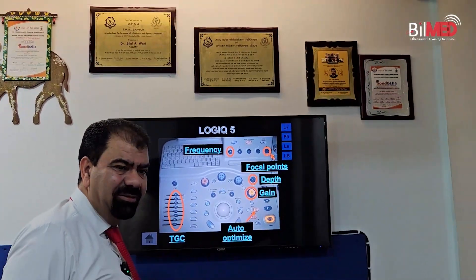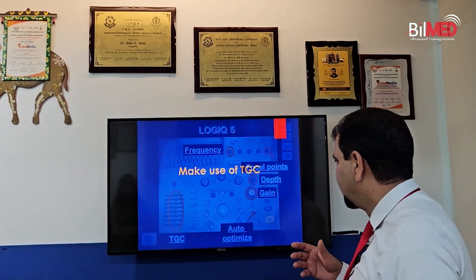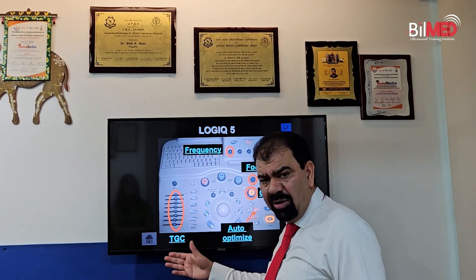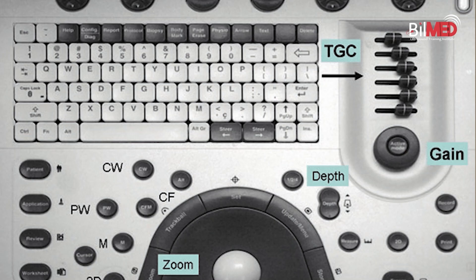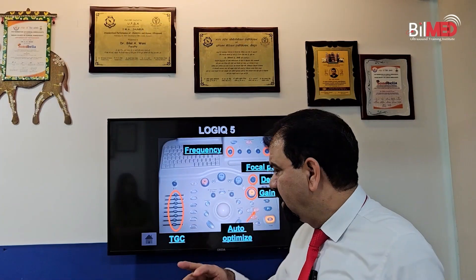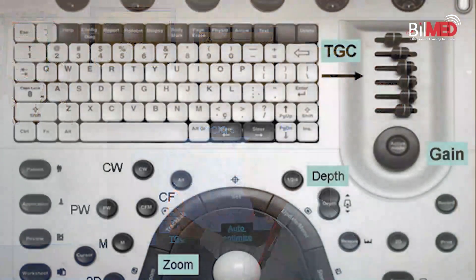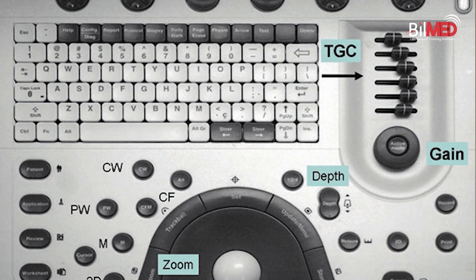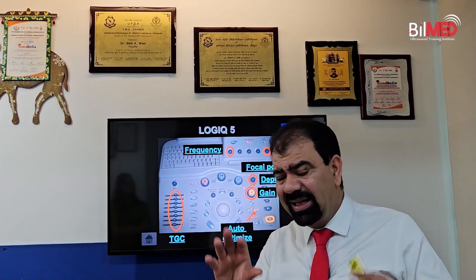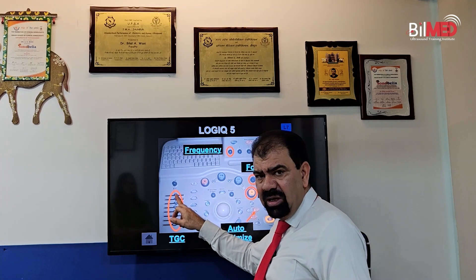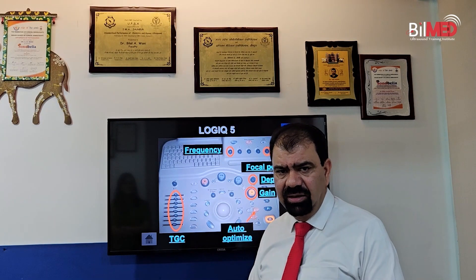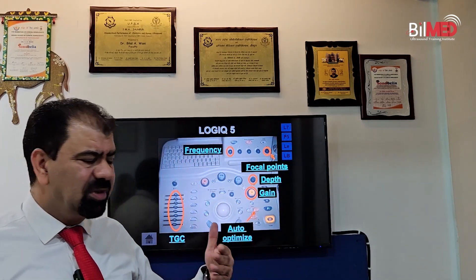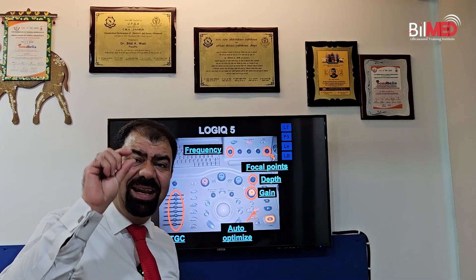Then the TGC. TGC is nothing but the gain of a specific area. For example, if you want to decrease or increase the gain of the mid part of your monitor, the mid sliders of the TGC will work for the mid part of the screen. And if you want to adjust the upper or lower side of your monitor, the corresponding TGC sliders are used. So TGC is the gain of a particular area of the screen.